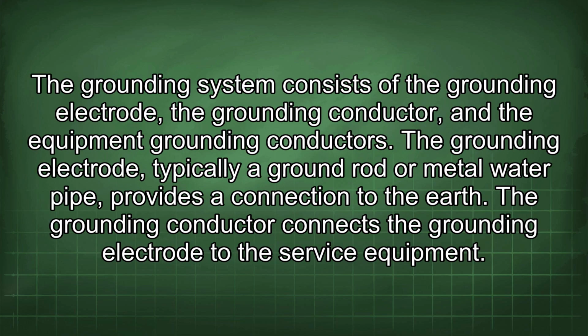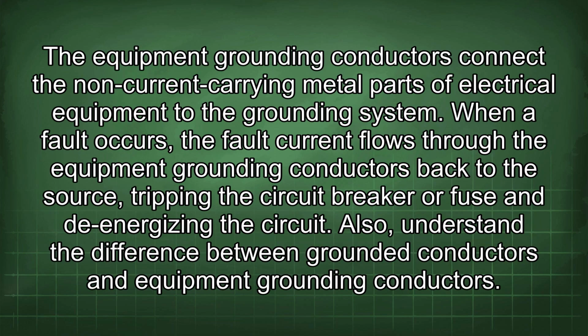The grounding system consists of the grounding electrode, the grounding conductor, and the equipment grounding conductors. The grounding electrode, typically a ground rod or metal water pipe, provides a connection to the earth. The grounding conductor connects the grounding electrode to the service equipment. The equipment grounding conductors connect the non-current carrying metal parts of electrical equipment to the grounding system.